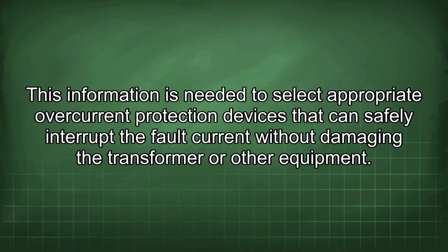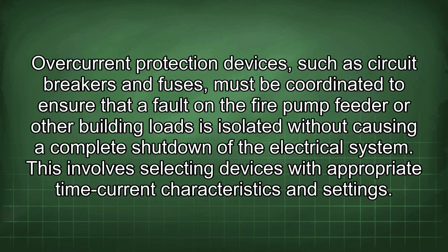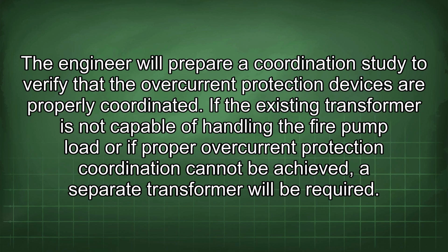This information is needed to select appropriate overcurrent protection devices that can safely interrupt the fault current without damaging the transformer or other equipment. Overcurrent protection devices, such as circuit breakers and fuses, must be coordinated to ensure that a fault on the fire pump feeder or other building loads is isolated without causing a complete shutdown of the electrical system. This involves selecting devices with appropriate time current characteristics and settings. The engineer will prepare a coordination study to verify that the overcurrent protection devices are properly coordinated.